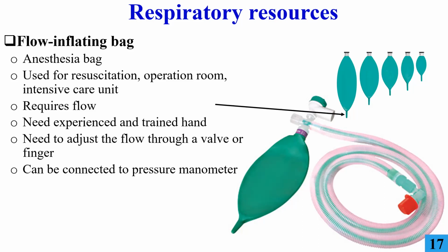So the good news about this bag is that it can give 100% oxygen. Also, when the baby is not ventilated, we will know because the bag will not be inflated. If the bag is not inflating, then either a safety valve is open, or there is a crack in the bag, or there is no tight seal, or there is no flow. So it's usually used only at the bedside or during surgery because it needs an air source and an oxygen source.